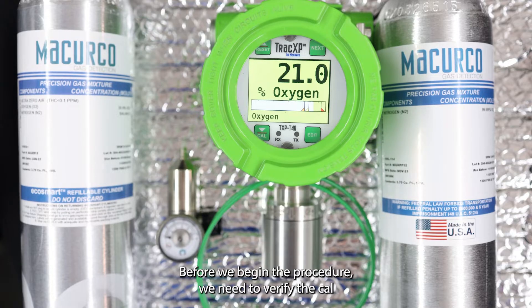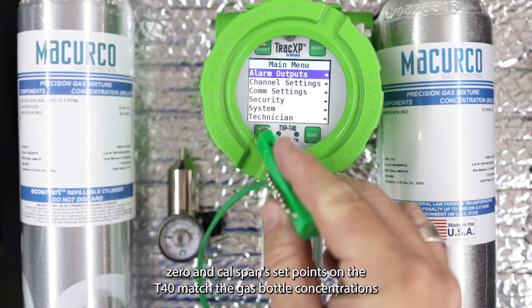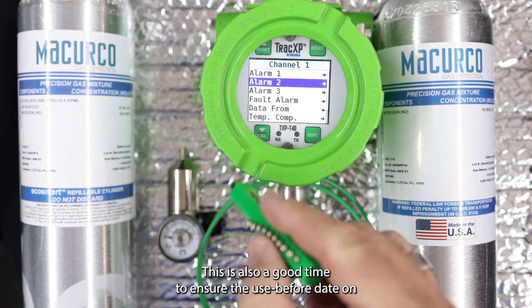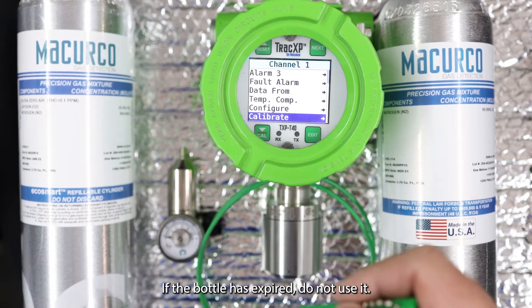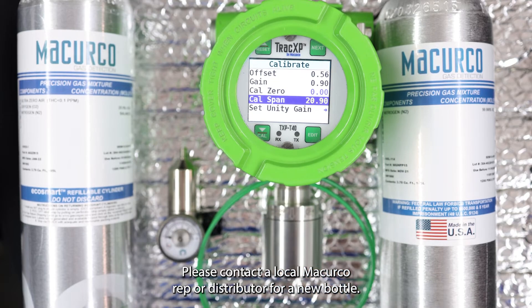Before we begin the procedure, we need to verify the cal zero and cal span set points on the T40 match the gas bottle concentrations shown on the labels — otherwise the calibration will not be successful. This is also a good time to ensure the use-before date on the bottles has not elapsed. If the bottle has expired, do not use it; please contact a local Macurco rep or distributor for a new bottle.